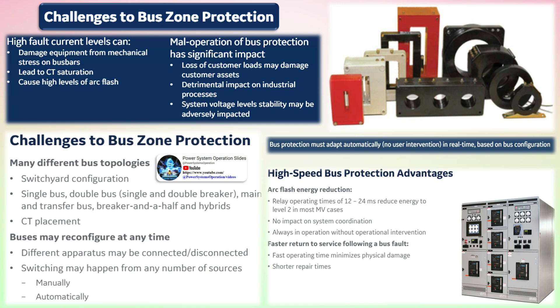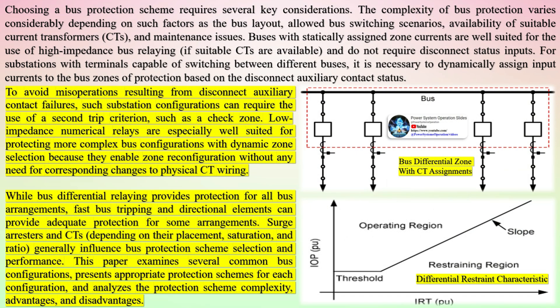To avoid misoperations resulting from disconnect auxiliary contact failures, such substation configurations can require the use of a second trip criterion, such as a check zone. Low impedance numerical relays are especially well suited for protecting more complex bus configurations with dynamic zone selection because they enable zone reconfiguration without any need for corresponding changes to physical CT wiring.